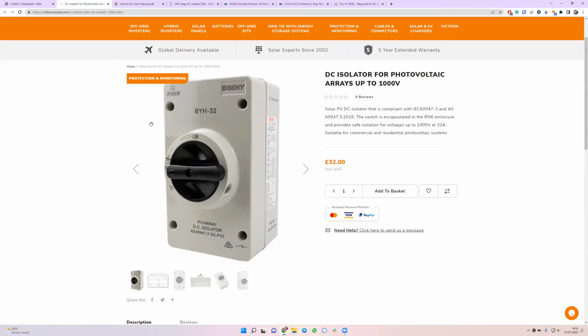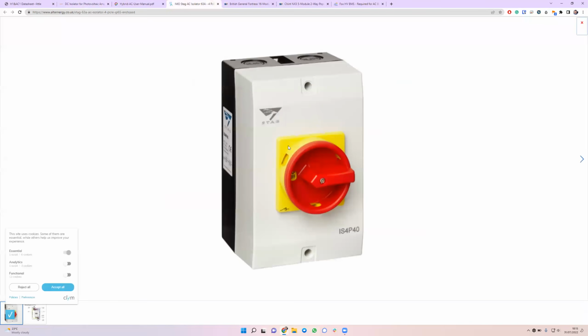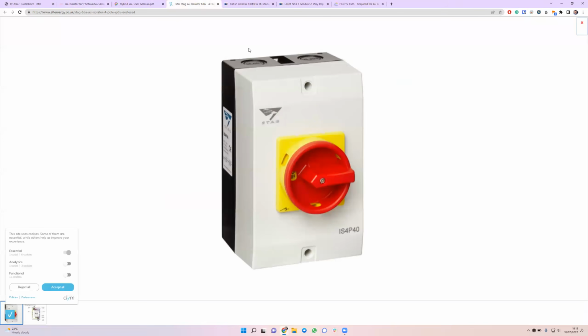If you're worried about the safety of the system, just isolate the AC as early as you can. If the AC has been turned off, so that is one of these, or the trip switches in any of these fashions, if anything is wrong with the inverter, just turn the AC off. What that does is it will actually de-energize the DC as well. It will cut all of the system eventually. It's not the best way. You should always isolate the DC first. But if there is a fault, you'll want to isolate the AC first.